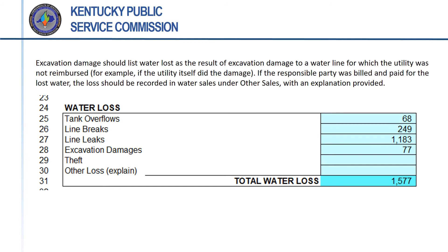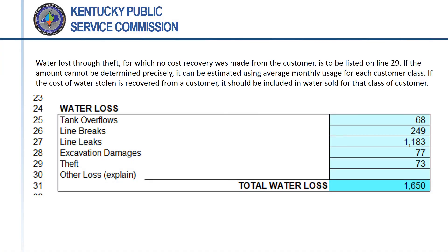Excavation damage losses should be listed on line 28 only if the utility was not reimbursed for the water that was lost. For example, if the utility itself broke a line during excavation, the water loss would not be reimbursed and the gallons lost should be listed on this line. If the responsible party reimbursed the utility for the value of the lost water, the quantity should be listed as other sales in the water sold section with an explanation provided. Keep in mind that paying to repair the damaged line is not the same as paying for the water that was lost — if the responsible party paid for repairs but not the water, the quantity lost should be entered on line 28.